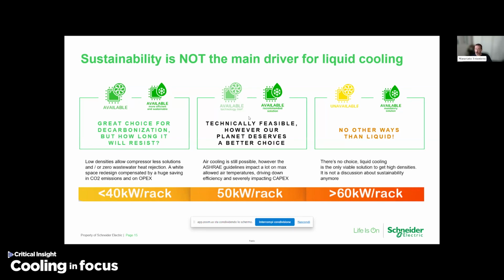Again, it's important to be clear on the messages. Many times people say liquid cooling is the only way to be sustainable. That's partially true. Liquid cooling is a great way to be sustainable for the current densities. For more than 50 kilowatts per rack it is the only way to cool a server. So again, saying that sustainability is allowed only by liquid is a partially greenwashing message.